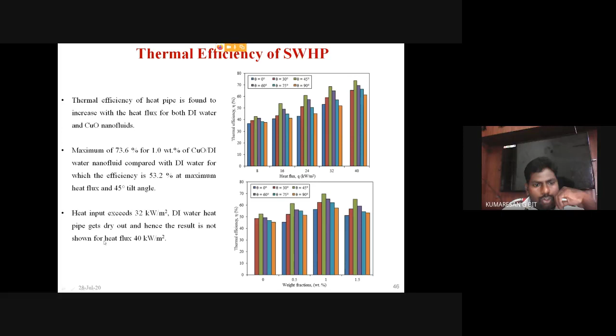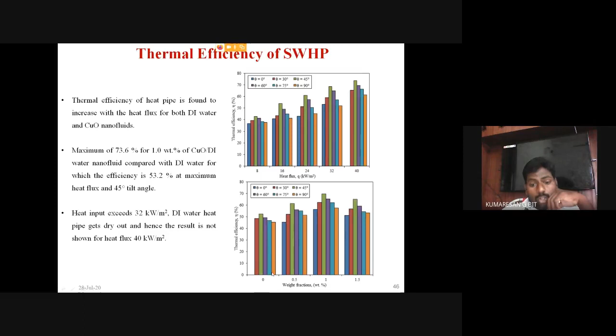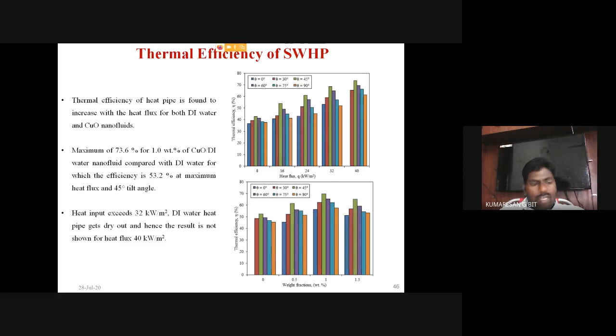Then when the heat input exceeds 32 kilowatt per meter square, the DI water heat pipe gets dry out, and hence the result is not shown for the heat flux of 40 kilowatt per meter square. Okay, so you see in the second figure, there is no blue color line indicated at 0 weight percentage, because the DI water heat pipe operating at 40 kilowatt per meter square heat flux may lead to dry out conditions. So that's why the heat pipes are not operating in that particular situation.